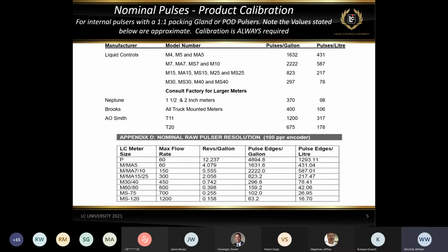is 2,222 pulses per gallon. If you remember, on an M7 meter, the meter puts out 5.555 revolutions per gallon. Well, on any of our electronic registers, we use what's called a quadrature pulse output. And those quadrature pulse output devices, our pulser, put out 400 pulses per revolution. So if you take the 5.555 and multiply that by 400, that's how we get this 2,222 pulses per gallon. So that's how we come up with a starting K factor. And that is based off of a 1-to-1 packing gland gear ratio.